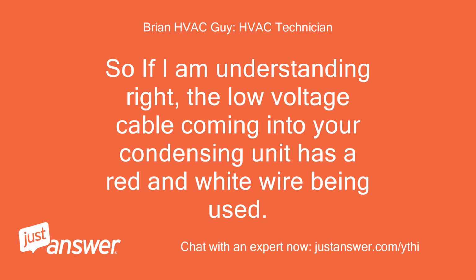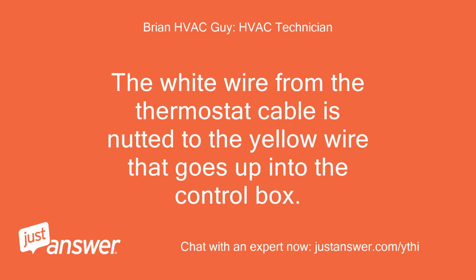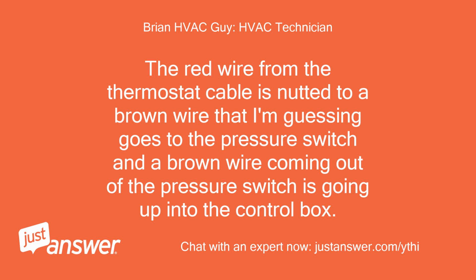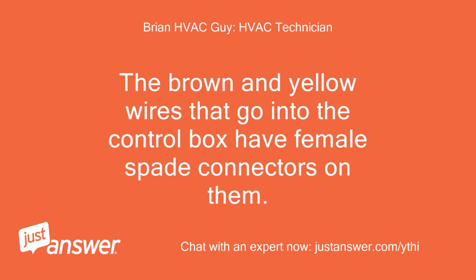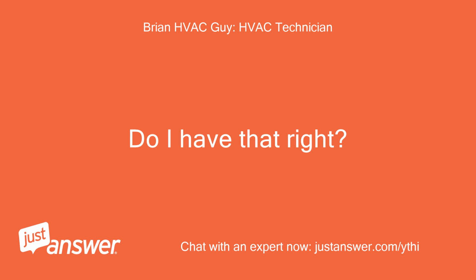So if I am understanding right, the low voltage cable coming into your condensing unit has a red and white wire being used. The white wire from the thermostat cable is nutted to the yellow wire that goes up into the control box. The red wire from the thermostat cable is nutted to a brown wire that I'm guessing goes to the pressure switch, and a brown wire coming out of the pressure switch is going up into the control box. The brown and yellow wires that go into the control box have female spade connectors on them. Do I have that right?